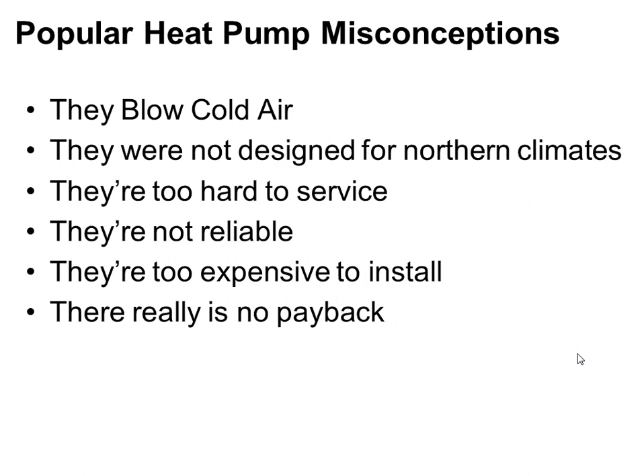The nice thing about the Infinity and Evolution is that there is no thermostat involved. We're using the Infinity and Evolution controller. It's 4 wires no matter what, A, B, C, D, and there's nothing else to think about whether you have a heat pump or an air conditioner. It wires identically. Everything's done over communication. So that's been easily resolved. Reliability issue. After prying into that one, most folks said they were concerned about longevity of a heat pump because you're running it so many more hours. There's numerous studies out there that show that heat pumps last just as long as air conditioners do, and in some cases even longer, and maybe that's because they're typically better maintained. But there has been proven to be no reliability issues with a heat pump as related to an air conditioner.